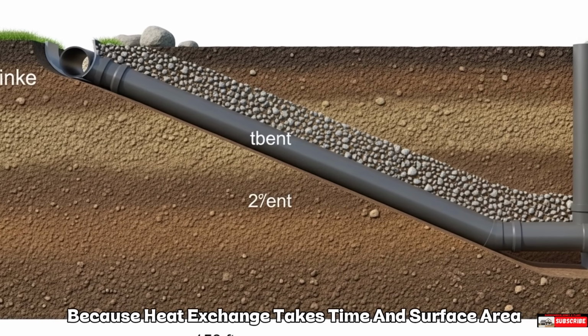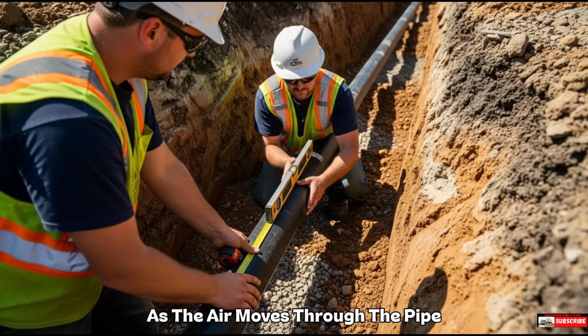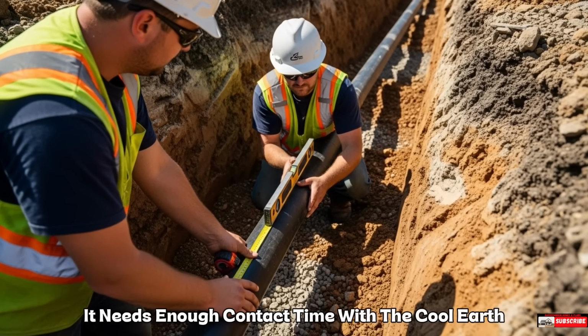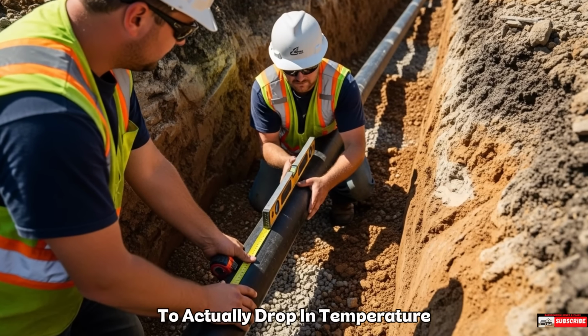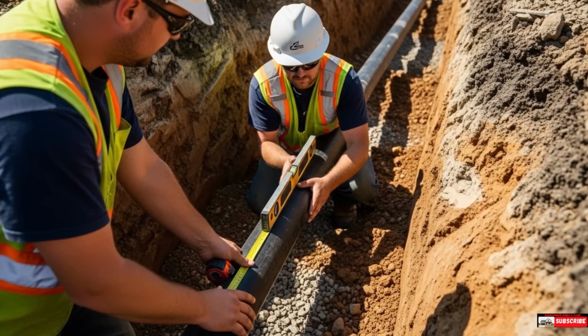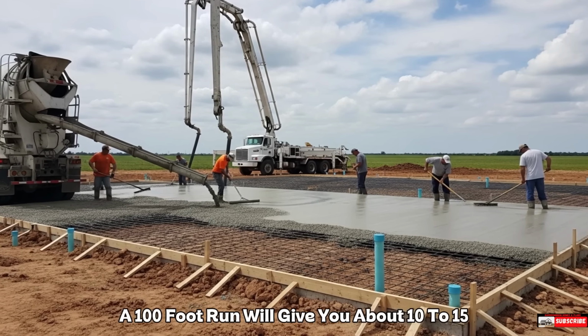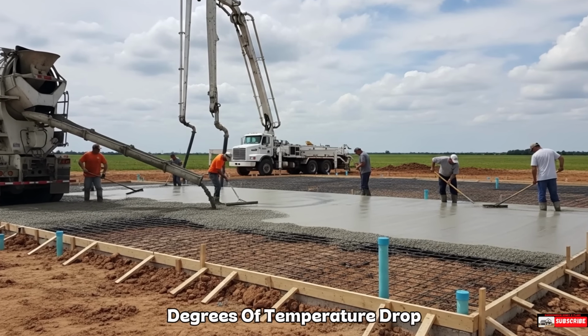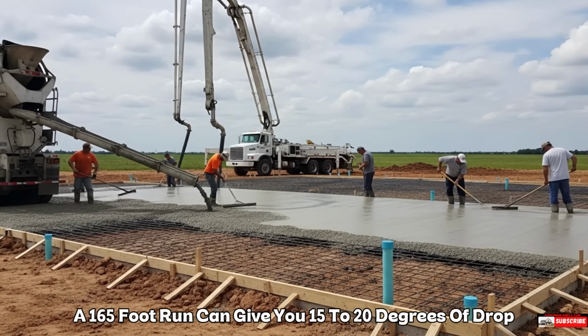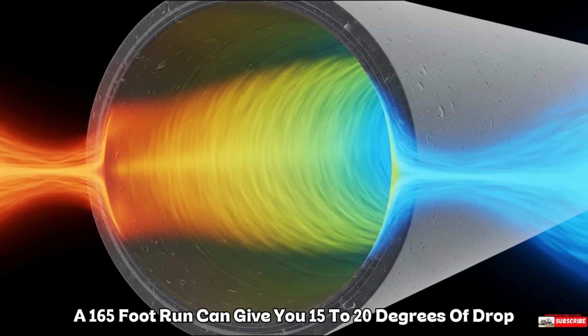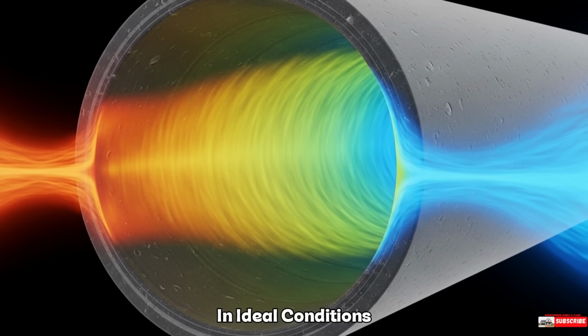Why so long? Because heat exchange takes time and surface area. As the air moves through the pipe, it needs enough contact time with the cool earth to actually drop in temperature. A 100-foot run will give you about 10 to 15 degrees of temperature drop. A 165-foot run can give you 15 to 20 degrees of drop in ideal conditions.